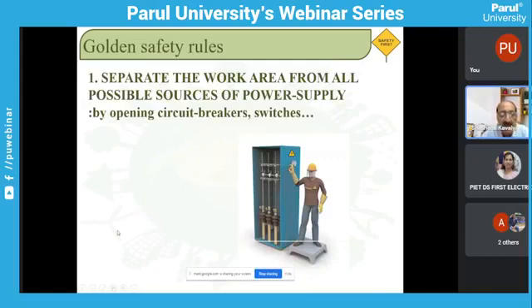Now, when you want to work, you must separate the work area from all possible sources of power supply. How do you do it? You have to cut off the switch, by handle or otherwise, by opening circuits. First you open the circuit breaker—that's automatic—then the isolator, which are switches you operate manually.